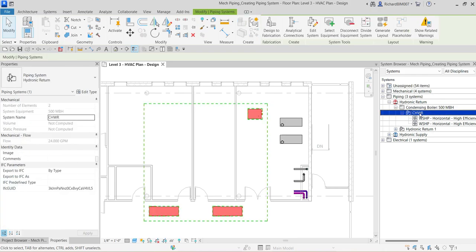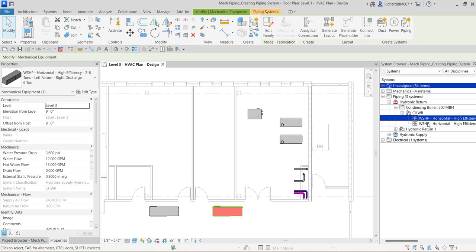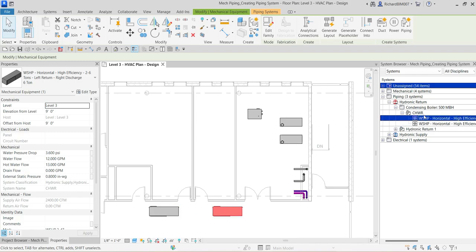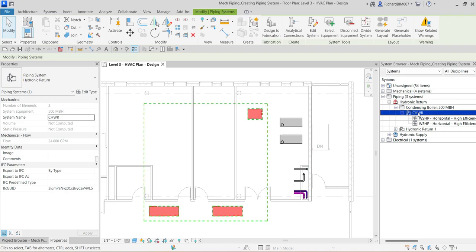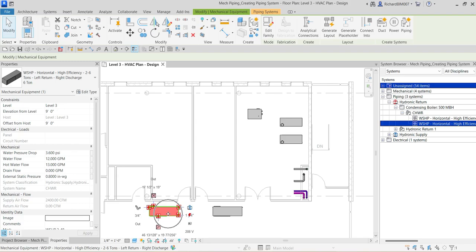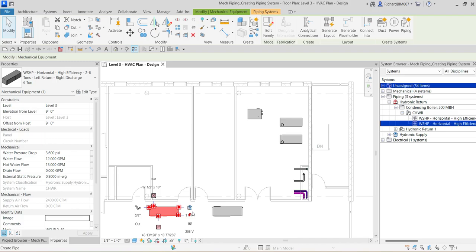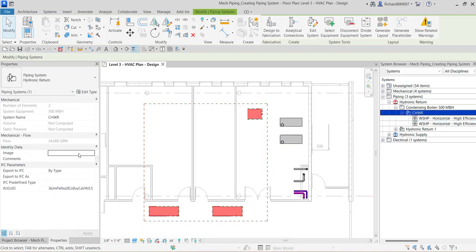The boiler is now on the hydronic return system. This is the name of the system, and these are the two water source heat pumps that are part of it. If I click the system, the total flow is 24 GPM. Each water source heat pump has a flow of 12 GPM, so 12 plus 12 equals 24 — that's why the system shows 24 GPM total flow.